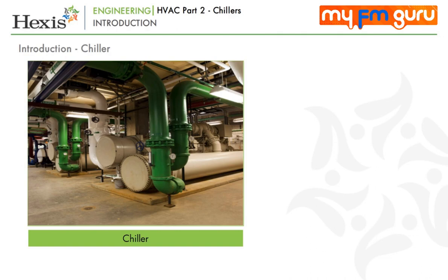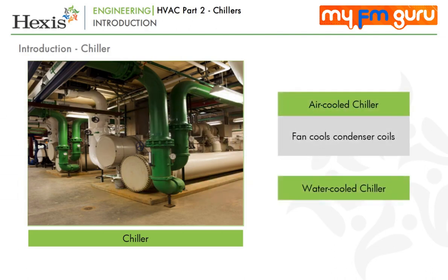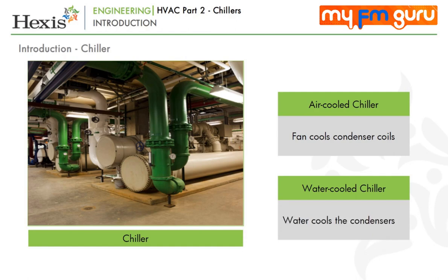Chillers can be broadly classified into two types by the manner in which the condenser is cooled: air-cooled or water-cooled. In air-cooled chillers, the condenser coils are cooled by a fan using ambient air. Water-cooled chillers use water to cool the condensers, and the cooling water in turn loses the heat gained to the ambient using external equipment such as an outdoor cooling tower.